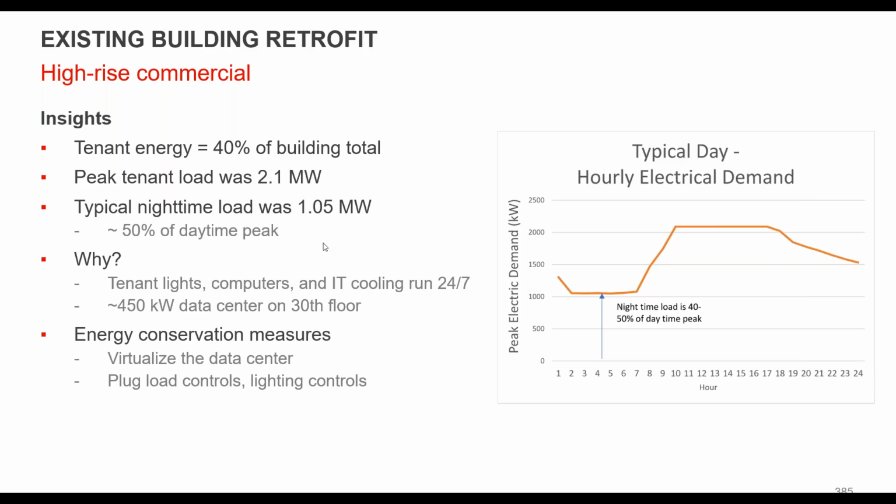And so that piqued our interest, and we started asking why. We went and talked to the chief engineer. We talked to who else was in the building, and we found a few interesting things. You'll see there's a consistent point here, a 450 kilowatt data center. We did not know about said data center. So that was running obviously 24 hours a day. That's about half of that nighttime.